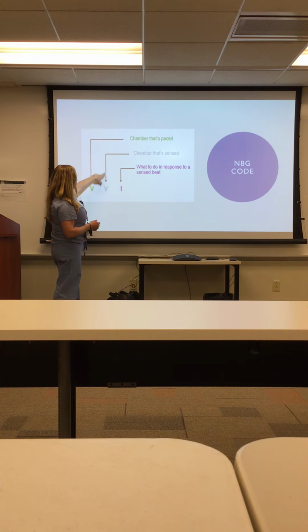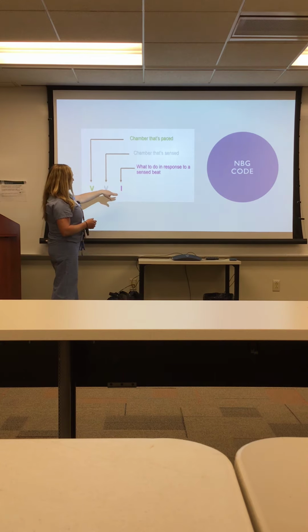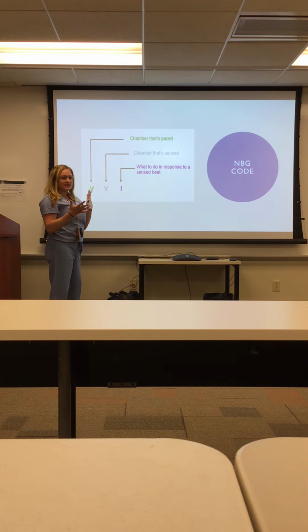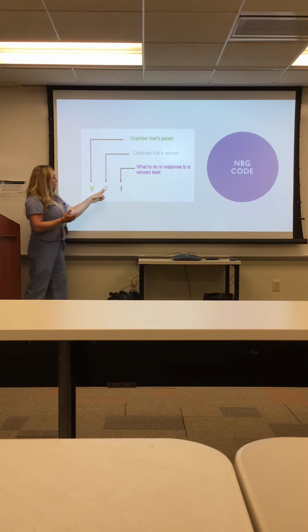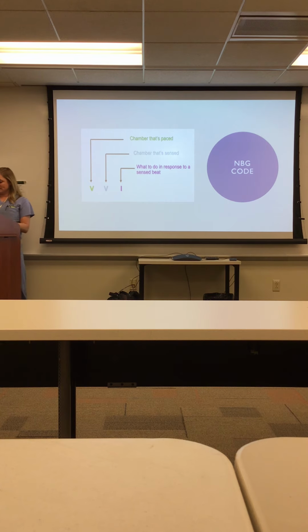The second one is the sensed. So it just looks at the sensing in the ventricle in this case. And then this is how the pacemaker will respond to it. So if it senses an intrinsic ventricular beat come through, then it's going to inhibit a paced beat from being delivered. If it doesn't see it in the appropriate amount of time, the lower rate, like 60 beats a minute, then it will deliver a paced beat. So it's all about what it's sensing and how it's going to deliver a paced beat.